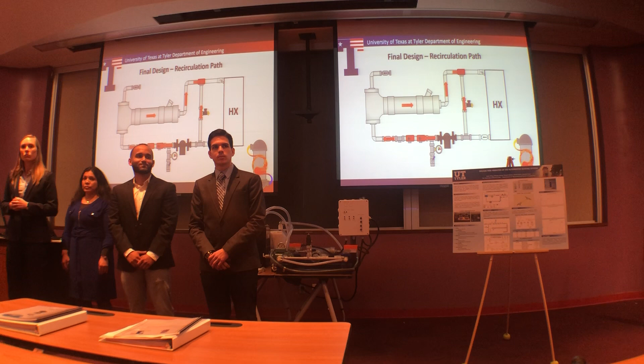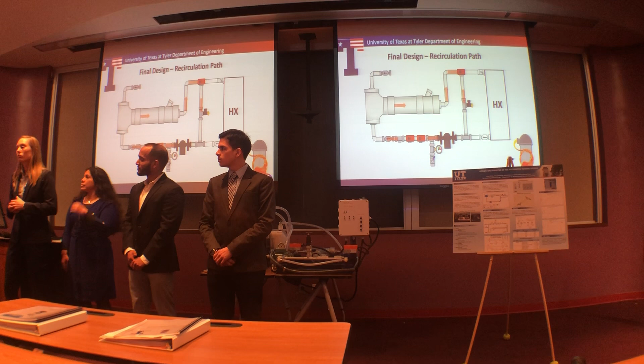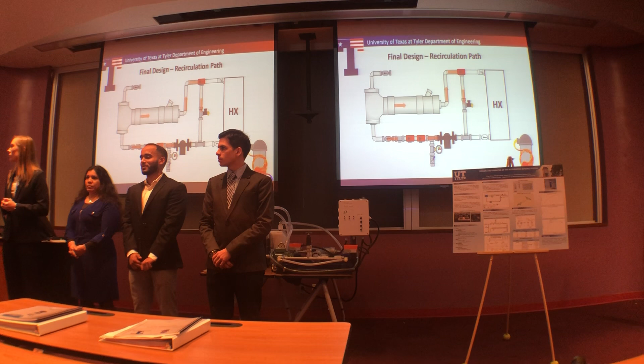Do you have an idea of the overall power requirements of your system? Electrically, we designed it with a 20 and 15 amp breaker. In total we have about 30 watts—actually the heater itself will take up to about 100 watts. But I know the breakers were much overrated for the actual use, and that was taken into consideration, with calculations done to make sure we're within the current ratings for each of the desired components.